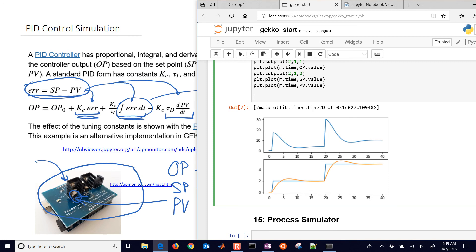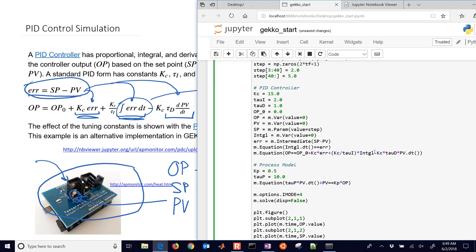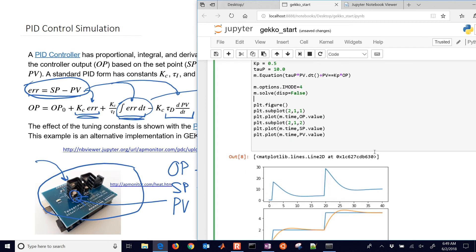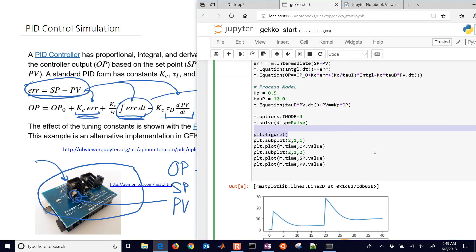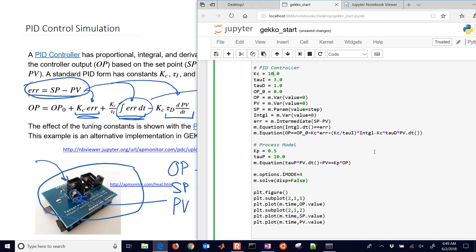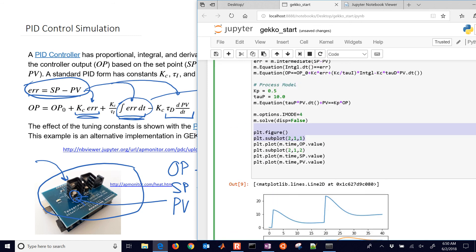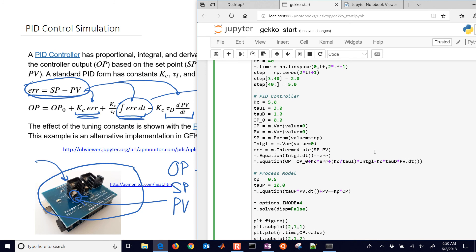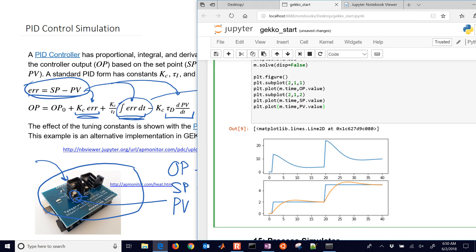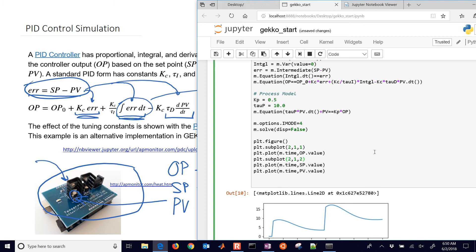One thing you can do is come in here and change the tuning parameters yourself. For example, if the response seems a little too aggressive, you can set tauI to 3 instead of 2 and dial back the gain as well. You can see the difference in tuning — running it shows a different response from your controller, making the process variable less or more aggressive in reaching the set point.